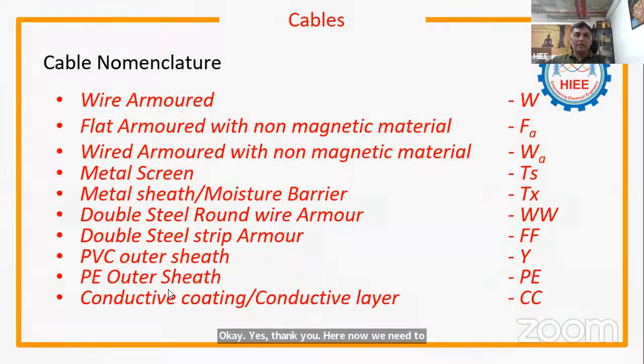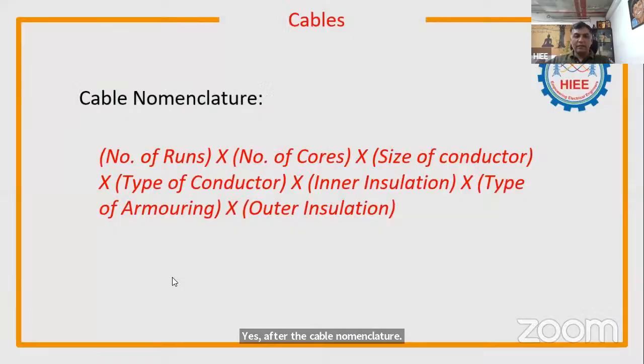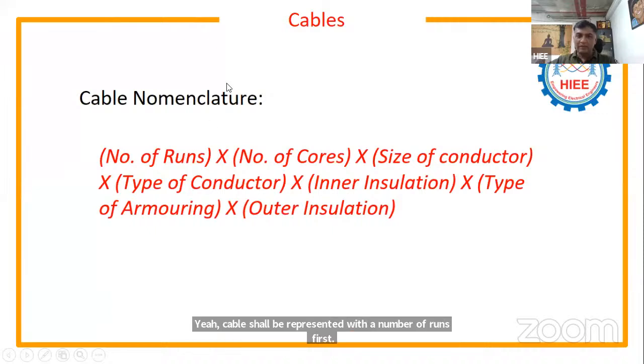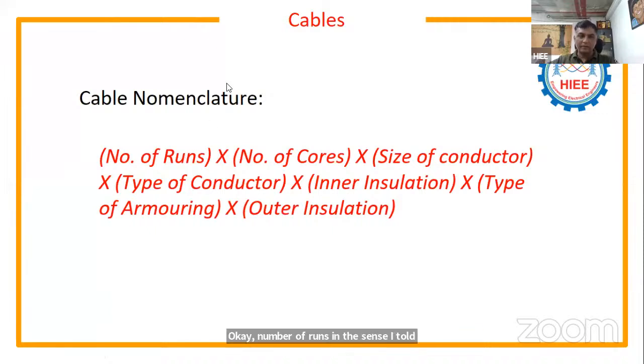Here, now we need to, after the cable nomenclature, here it is mentioned very clearly how to give the cable nomenclature. First, a cable shall be represented with the number of runs. Number of runs, as I told you now, for example 2 runs. Then number of cores, let me take 3 core. Then size of the conductor, which depends upon the current carrying capacity. Let me take 150 square mm as the size of the conductor.